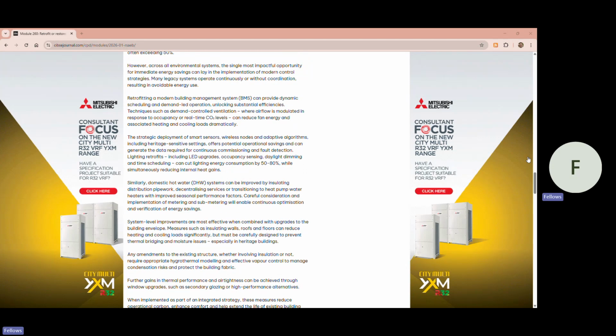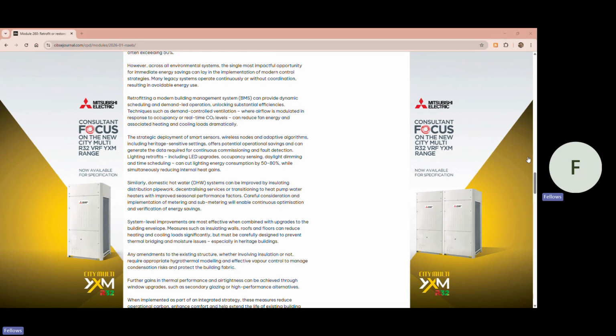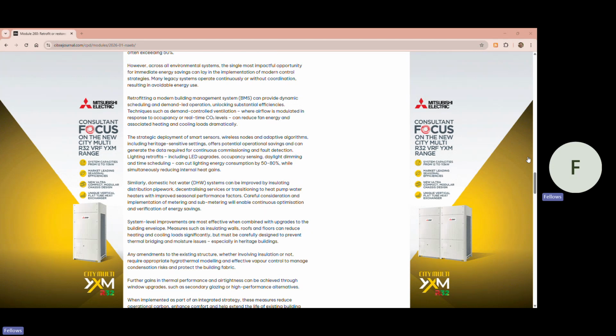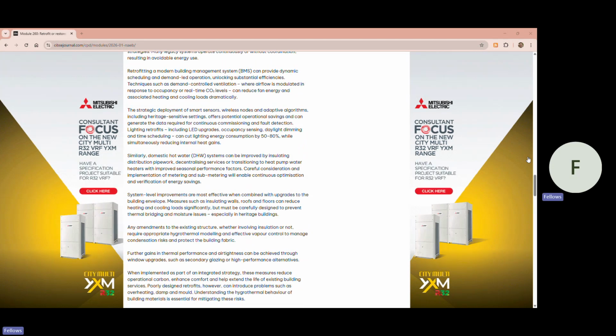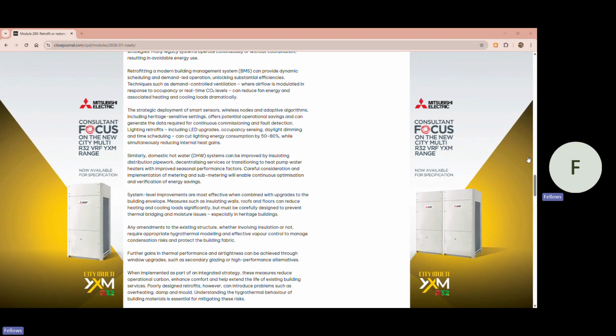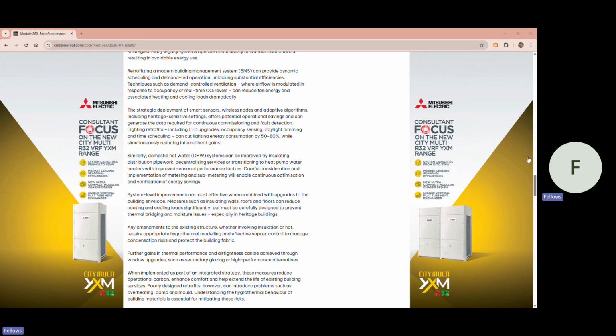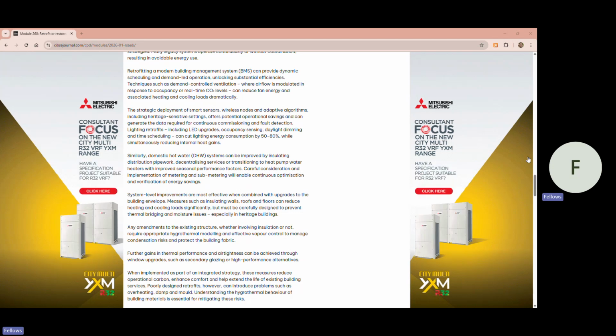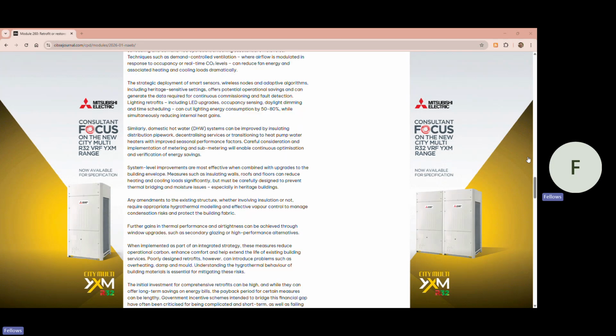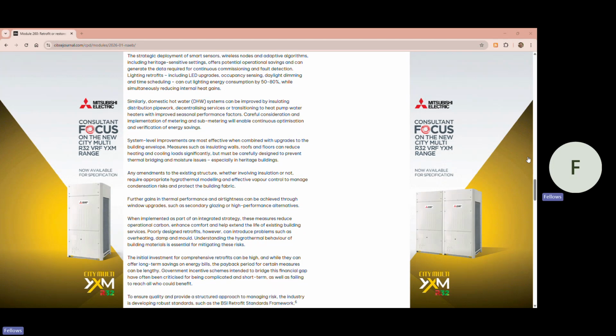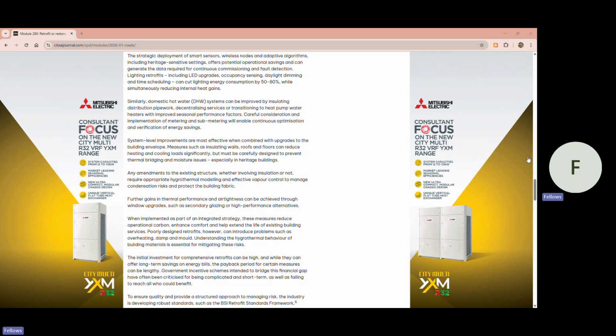Lighting retrofits, including LED upgrades, occupancy sensing, daylight dimming, and time scheduling, can cut lighting energy consumption by 50 to 80%, while simultaneously reducing internal heat gains. Similarly, domestic hot water (DHW) systems can be improved by insulating distribution pipework, decentralizing services, or transitioning to heat pump water heaters with improved seasonal performance factors. Careful consideration and implementation of metering and sub-metering will enable continuous optimization and verification of energy savings. System-level improvements are most effective when combined with upgrades to the building envelope.